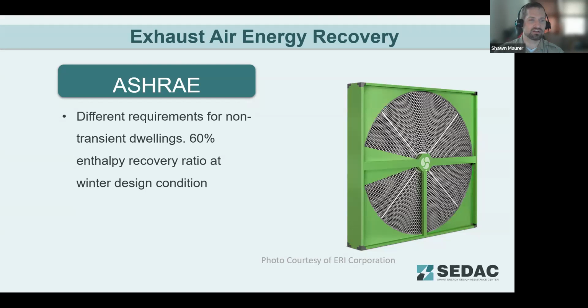For exhaust air energy recovery, ASHRAE does have similar requirements to the IECC for the most part, but ASHRAE also has some requirements for non-transient dwellings, including needing 60% enthalpy recovery ratio for the winter design condition. That's the big difference here between ASHRAE and the IECC's energy recovery systems. There are a lot of different ways to achieve that 60% enthalpy recovery. Heat wheels are the most likely in commercial buildings as compared to a static core that's found in a lot of residential applications. It has a little bit lower efficiency ratio typically. So this ASHRAE requirement may start seeing, with ASHRAE compliance, a little bit more proliferation of energy wheels into residential and long-term dwelling requirements.